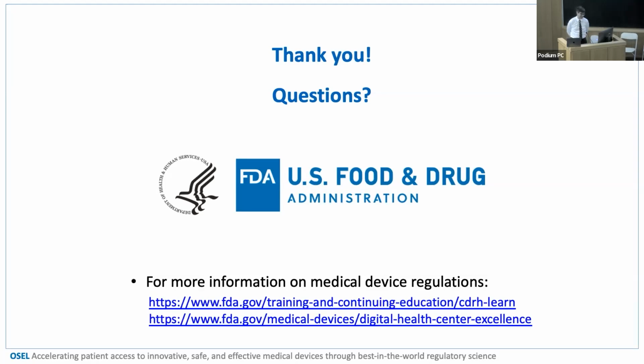Yes, I totally agree. As a scientist, it's concerning, but usually these indications for use don't have numerical values. That makes me a little nervous because different hospitals have different protocols. So even if you say 20% dose reduction, maybe the hospital next door has a protocol that has 20% dose reduction already. But still, the way it was finally agreed on, I think it's clear. It says it's in phantom studies, and everybody can see the phantom. It's publicly defined, this MITA phantom. So yes, the end user has to be aware that those results may vary in practice.